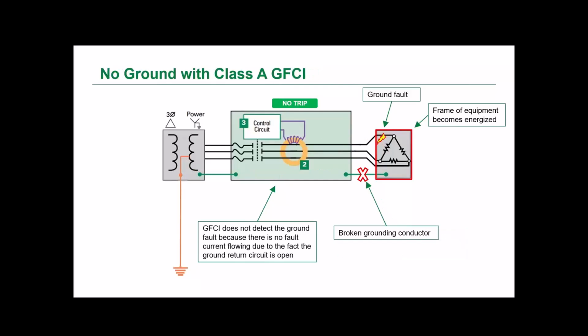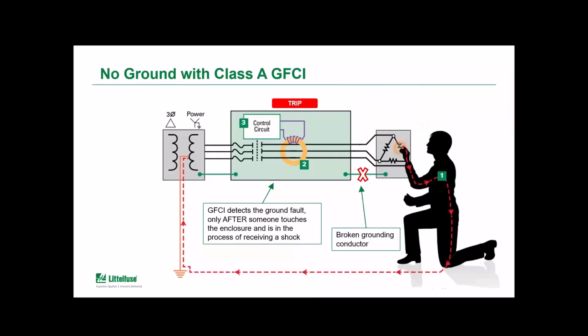Now, if we take the same case with the ground fault, but now we add a broken ground conductor that has occurred at the same time, this will interrupt the ground return path. And because that path is interrupted, there is no path for that fault current to flow back to the power source. That means the GFCI will not be able to trip. So the net result is the frame becomes energized at line to neutral, potentially giving someone a shock if they come into contact with it. So when somebody does make contact and the fault current is flowing through them, the GFCI will be able to measure that and trip, again, as specified by the standard. So the GFCI will stop the shock very, very quickly and probably save this person's life, but the shock does begin to occur before the GFCI can take that action.